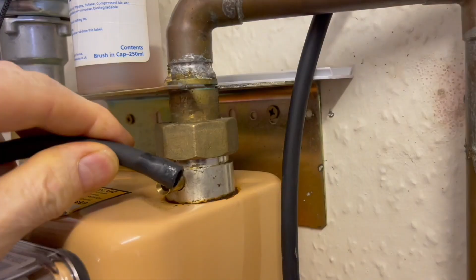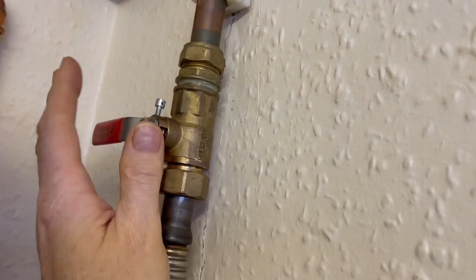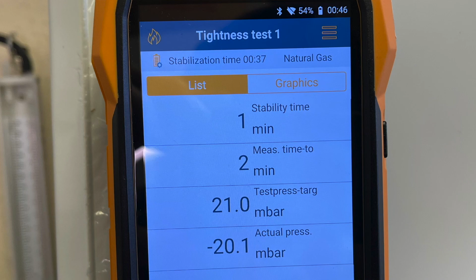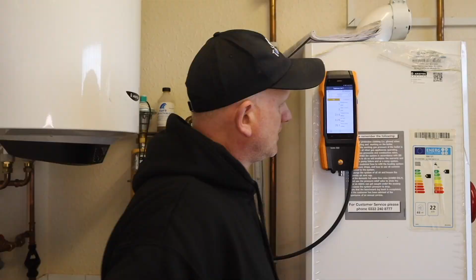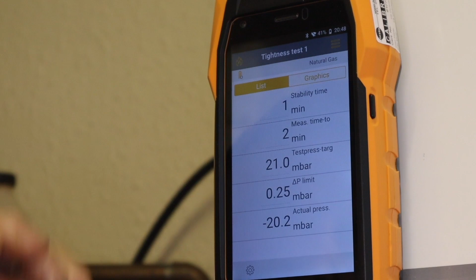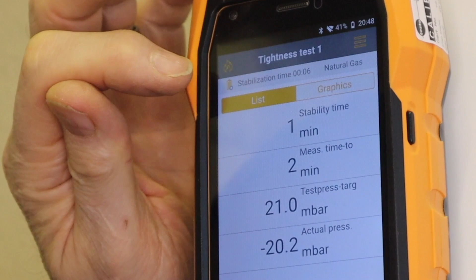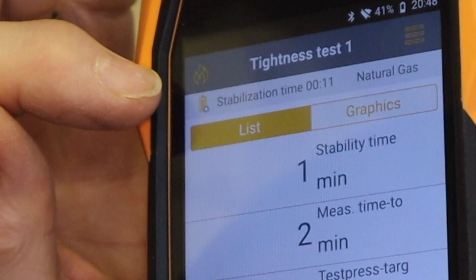Again, I need to put this onto my gas meter, and again, I need to add some pressure in there. So you can see I've got 23 in there, so I just need to drop it down a bit, between 20 and 21. So you can see I'm just over the 20 now, so we're at 20.1. So I need to press the center again, and what it's going to do now is go through its stabilization time. It starts now, and you can see at the top here it's counting down now, its temperature stabilization like it did on the last one.